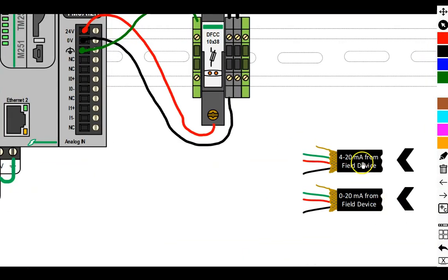It's working right now. On these, what we see is that we've got a shielded cable coming in. And that means that we've got a positive and negative signal. We've got a ground that is inside of the cable. Not all cables have the ground inside. But then we also have got this shield that's going to be around the outside over here. The shield should be connected on the sourcing end, and then it should be disconnected on the far end. You never connect both sides of the shield, just the one end. Isolate it, tape around it or something like that at the far end.